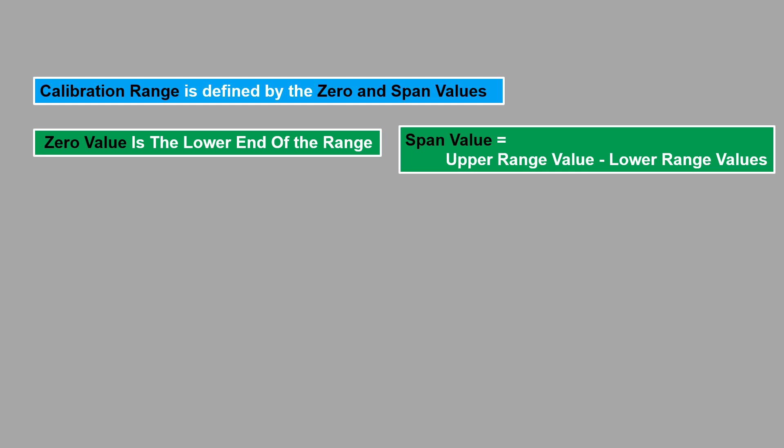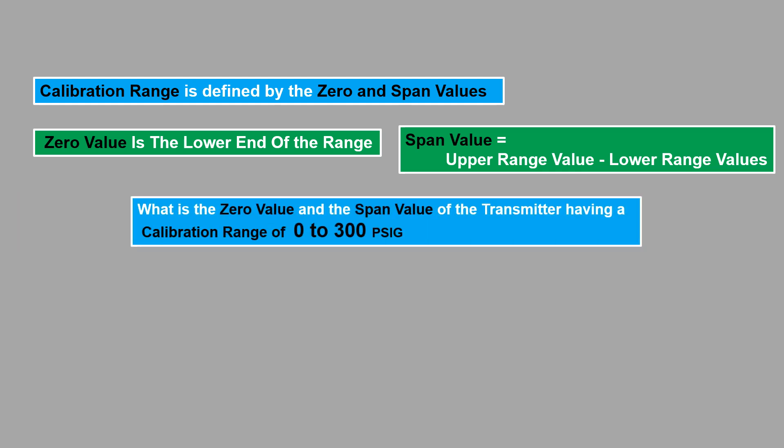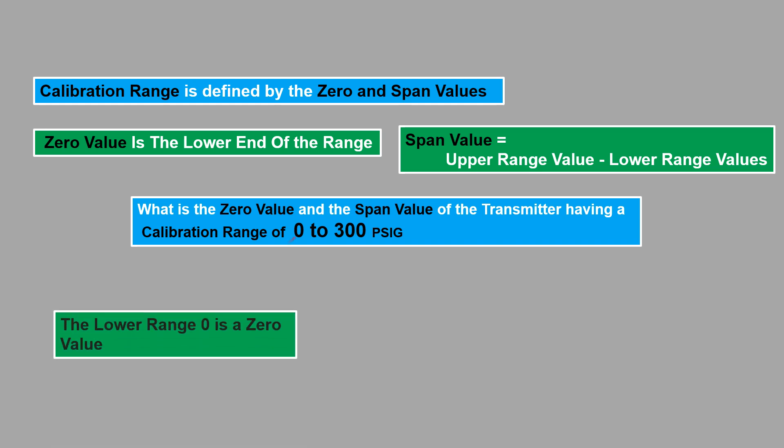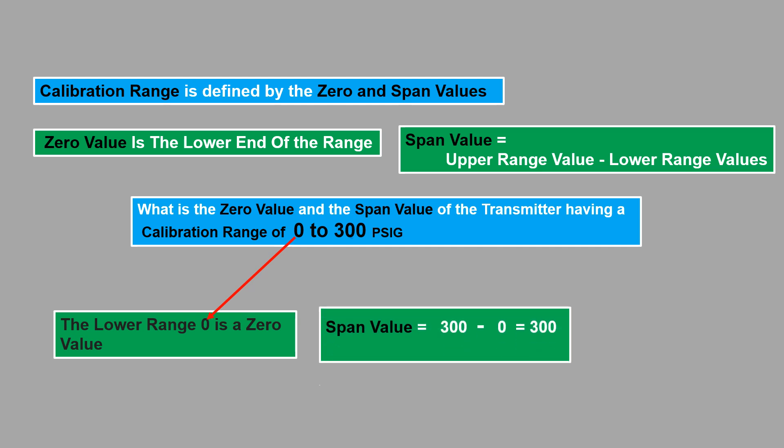Now let's check what is the zero value and the span value of the transmitter having a calibration range of 0 to 300 psig. Here the lower range 0 is the zero value and the span value is the algebraic difference between the upper and lower range values. That is, here it is the difference between 300 and 0 which is 300 psig.